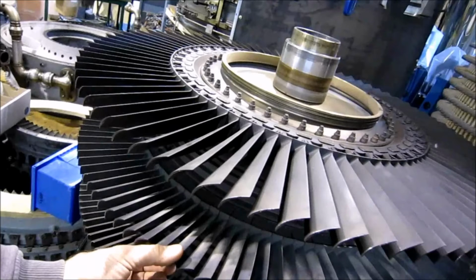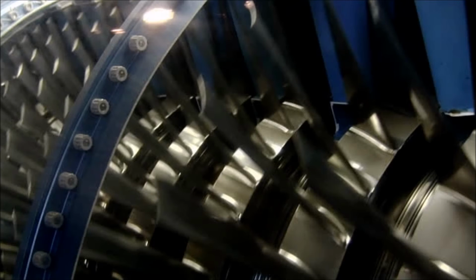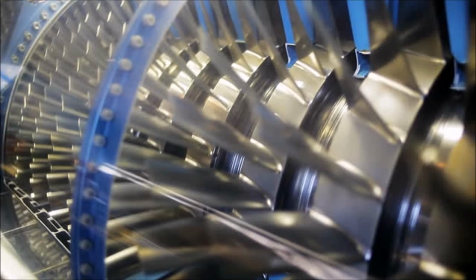B. Based on arrangement of compressor motor or external drive: 1. Open type. 2. Hermetic, or sealed, type. 3. Semi-hermetic, or semi-sealed, type. In open-type compressors, the rotating shaft of the compressor extends through a seal in the crankcase for an external drive. The external drive may be an electrical motor or an engine, for example a diesel engine. The compressor may be belt-driven or gear-driven.